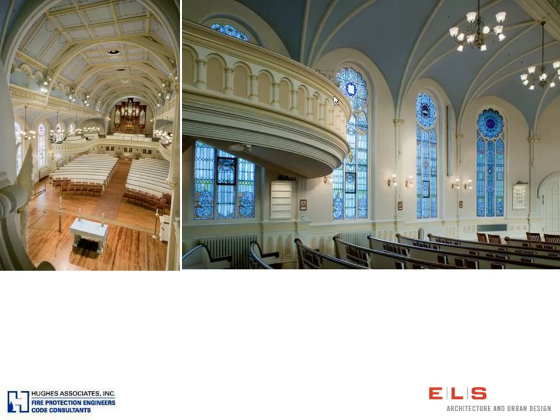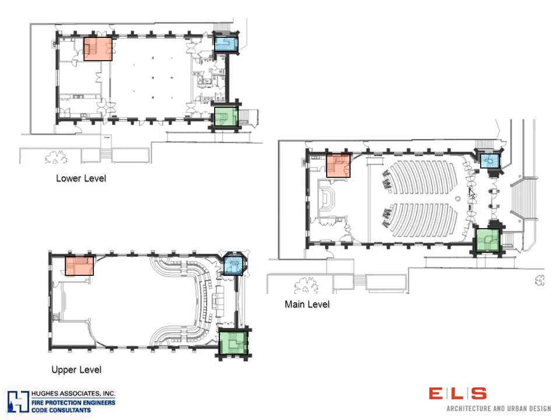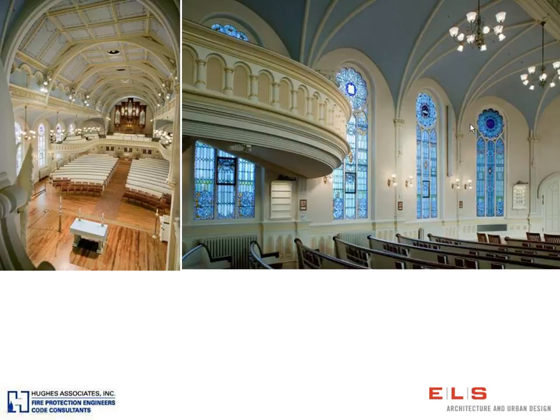So oftentimes when we do property line, oh, sorry, now I have to go back. What Kurt was describing, these windows are very close to a property line, and in addition to that, the egress path is on the outside of these windows. And oftentimes when we provide sprinkler protection to protect at an opening, and in the fire protection world, an opening means any opening in a wall, so a window is an opening, we oftentimes protect with sprinklers that are directly over the space of the opening. And when we do that, there are rules that we have to follow about no horizontal mullions and how close they need to be, and other special rules for what we call exposure protection.